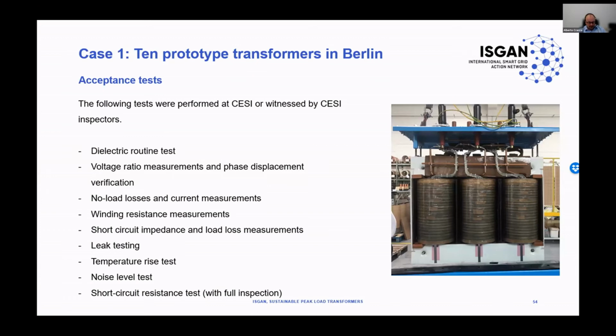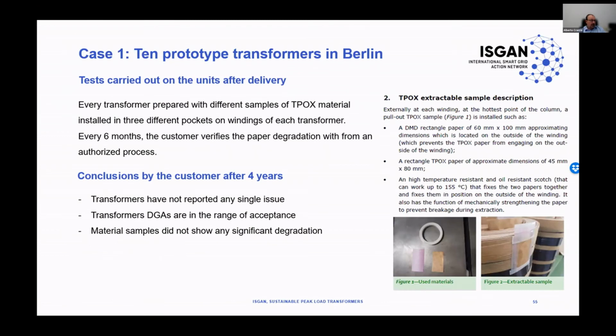Moreover, if we go to the next slide, please, the OEM and the customer wanted to do some additional tests during the lifetime of the transformer. In the preliminary phase, before entering into a contract with a utility, we agreed on a way to test the insulation material that we use for manufacturing the windings during the lifetime of the transformer. In order to do that, we defined a special pocket inside the windings where we install some samples of paper and material that can be extracted by the utility during the lifetime of the transformer itself. This procedure was agreed, obviously, between the quality guys of the utility and the engineers that designed this transformer.